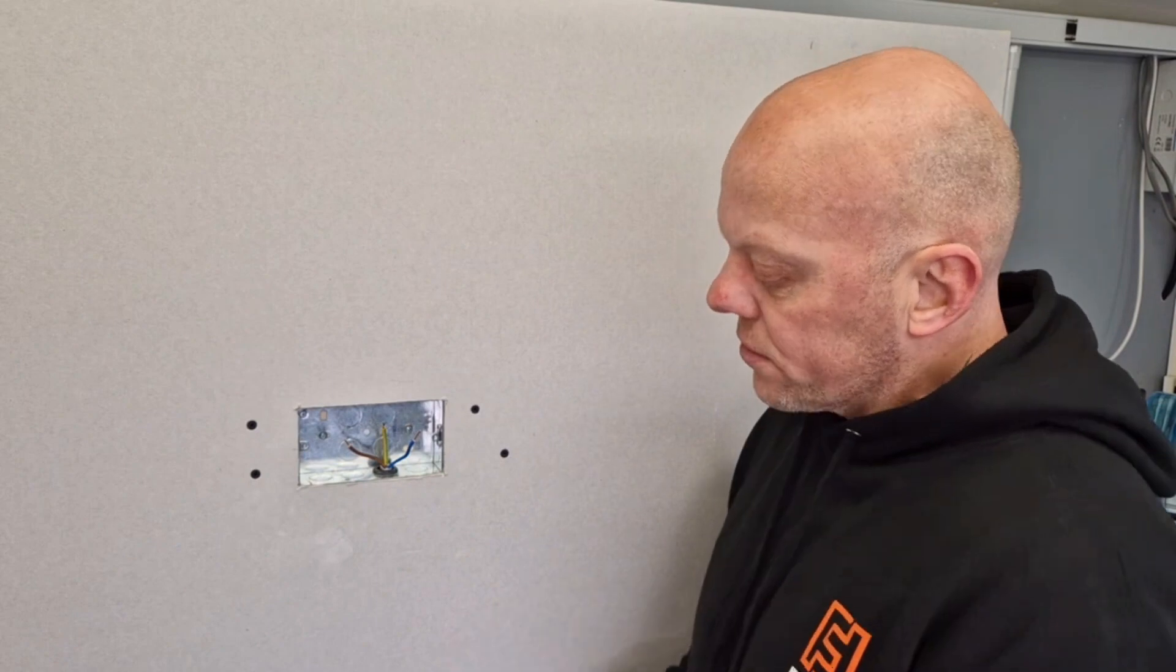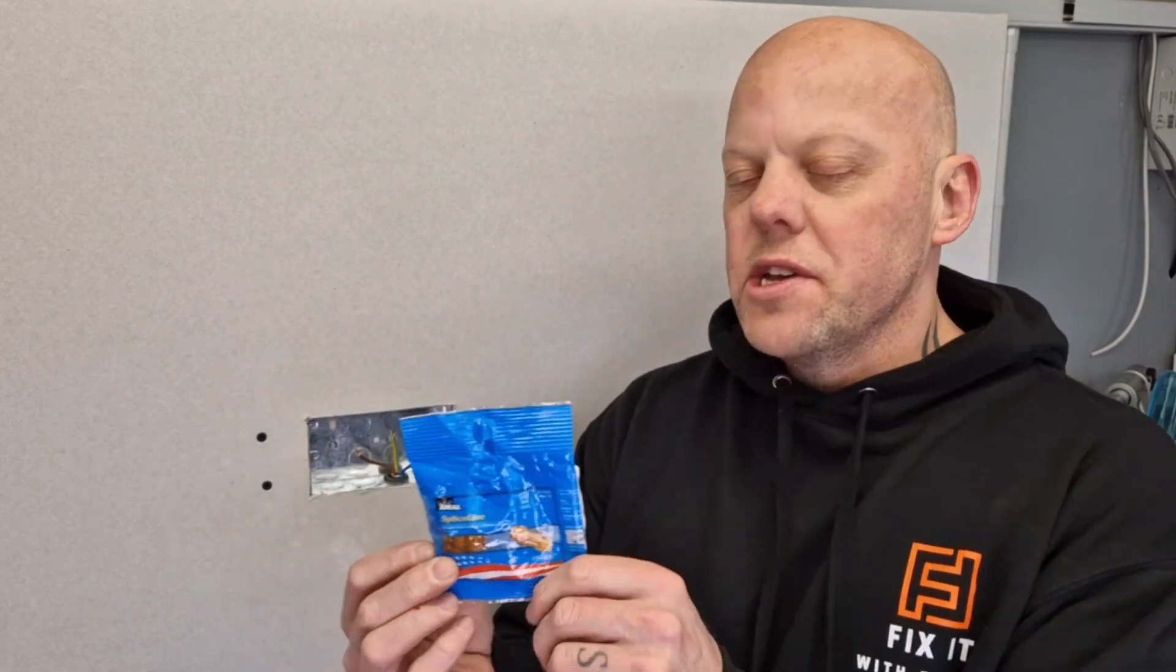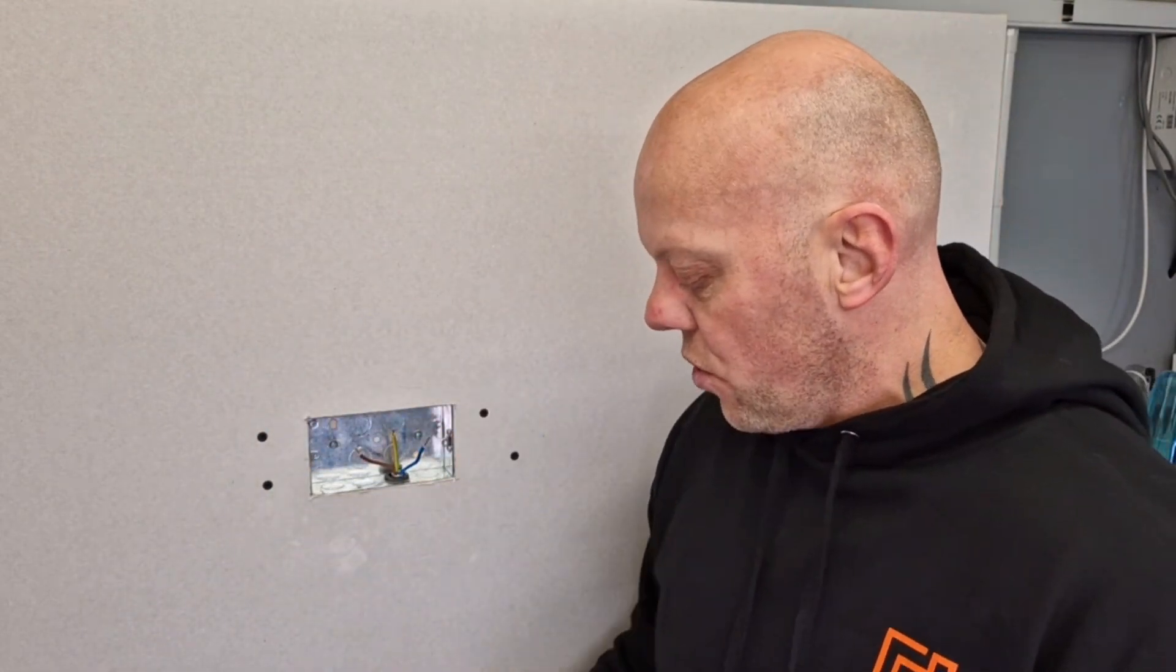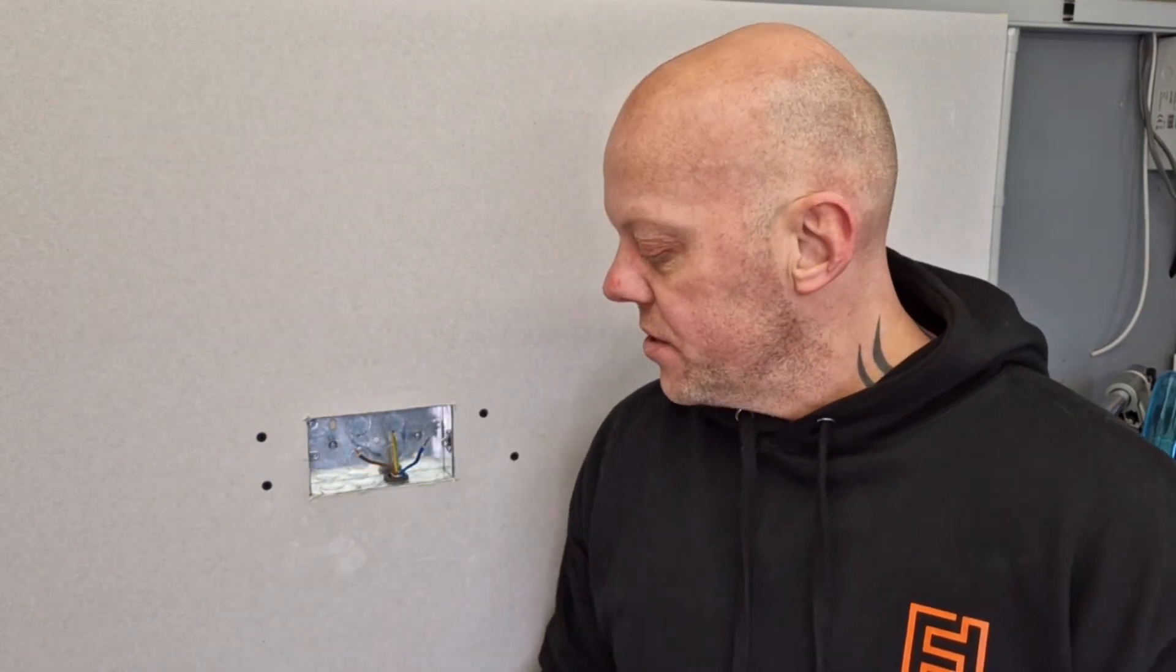So the best method to extend these cables is these splice line connectors. Now these are ideal for this sort of job - they are pretty small, they don't take up much extra room in the box, they're rated up to 32 amps, so these are ideal for this job.